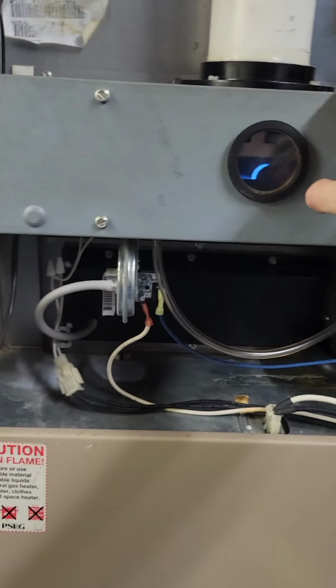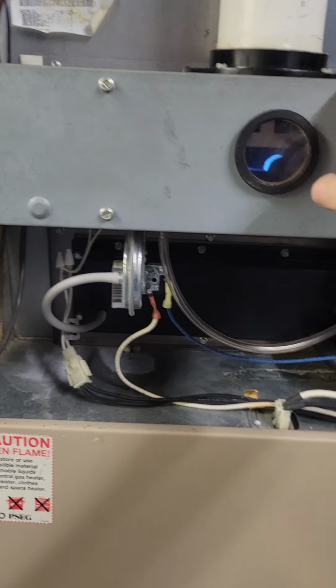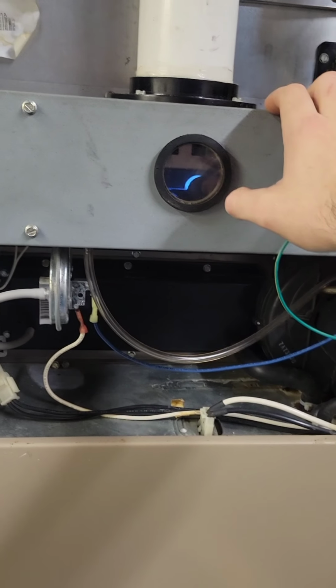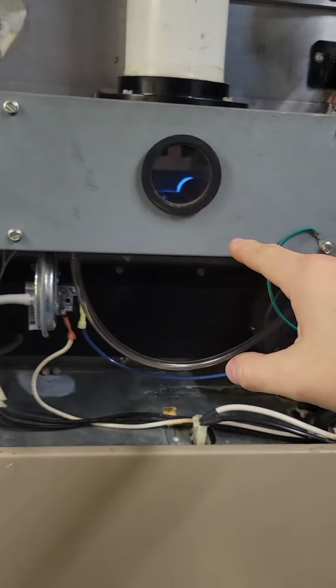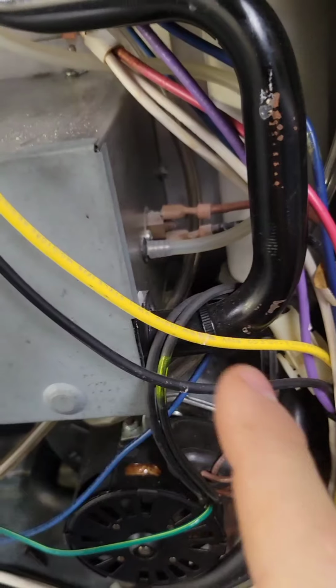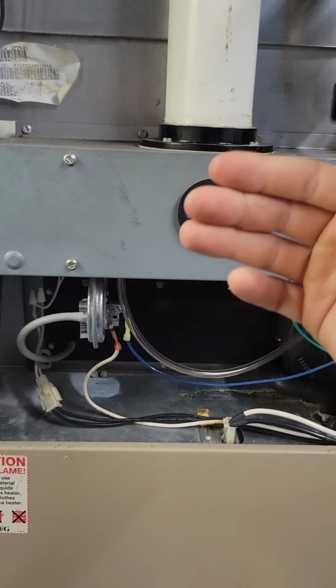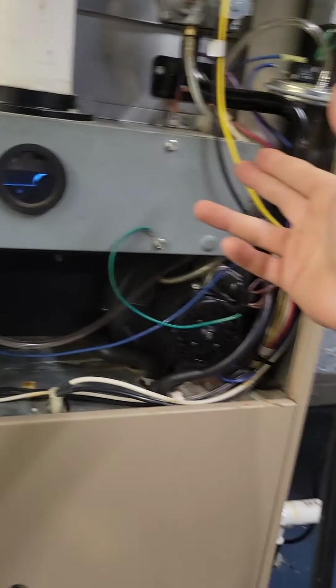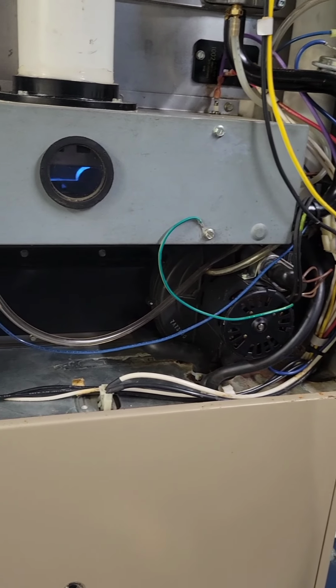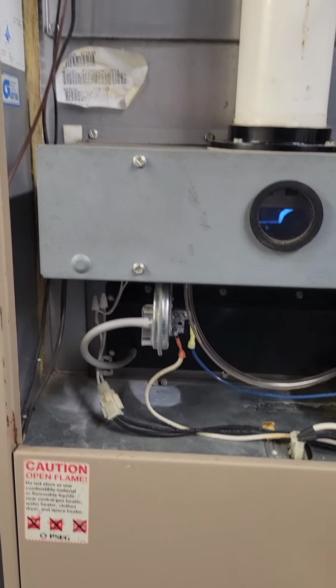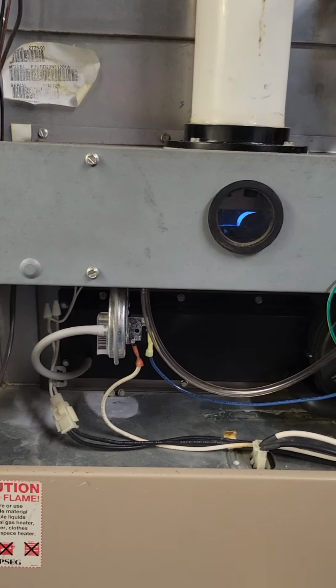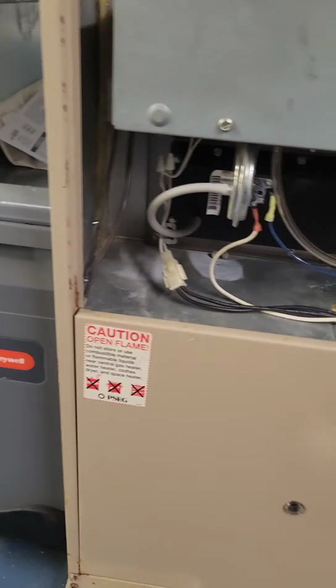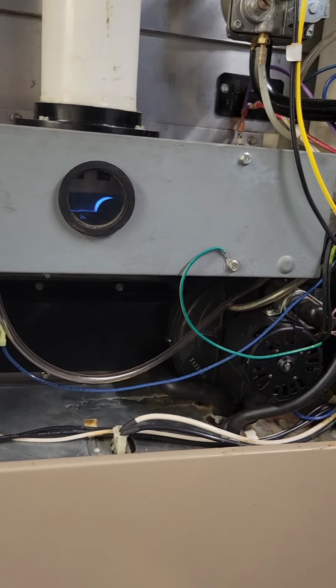So even though this guy's old, it still has a pretty good amount of safety switches built into it. There's rollout sensors located on the inside and on the side here. So that little brown guy right there you see, it's a rollout. So in the event that the flame was to come back or roll out, it'll overheat and trip that limit, and then obviously tell you there's a problem. So yeah, filter's already been changed, so we took care of that. But yeah, just like a basic maintenance, nothing crazy.